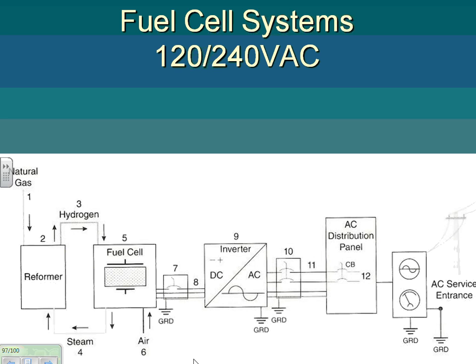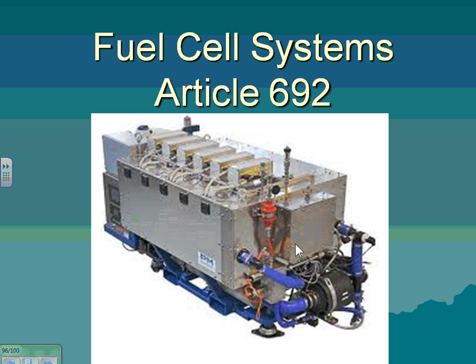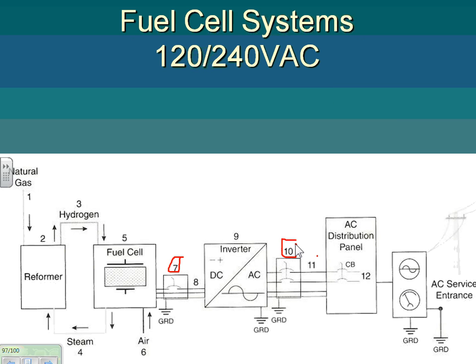I just want to emphasize very quickly the disconnect. Does that look familiar to you? The system has to have a disconnect here, and the inverter also has to have a disconnect. Can you guys see that? You generate, in this case, DC. There is no AC. You generate DC from the fuel, and DC is beautiful because we can invert it. And then you have to have a disconnect to disconnect that system that looks something like this. And you're going to disconnect it completely for safety.